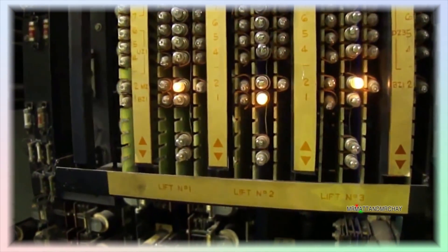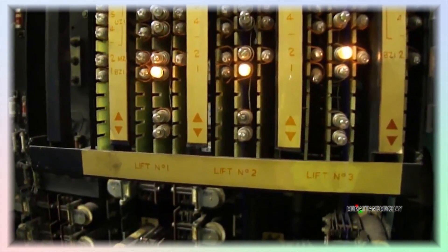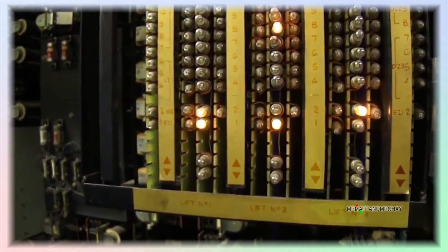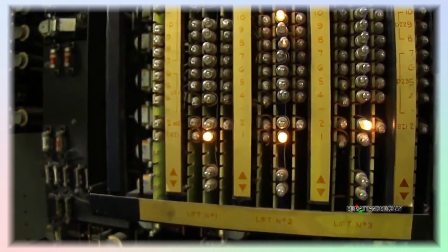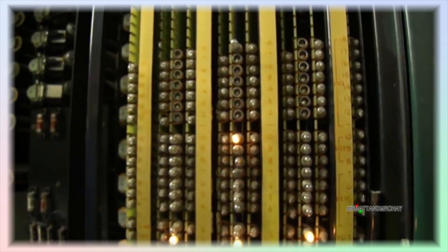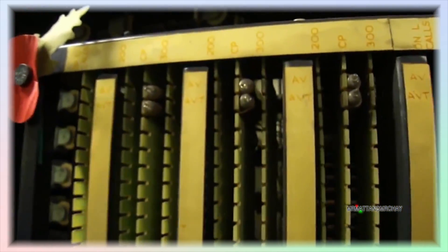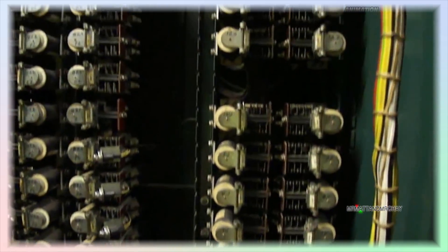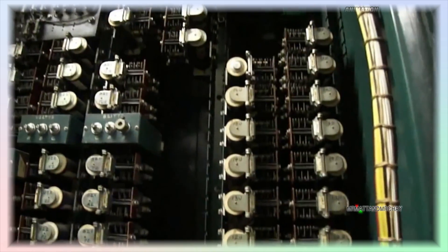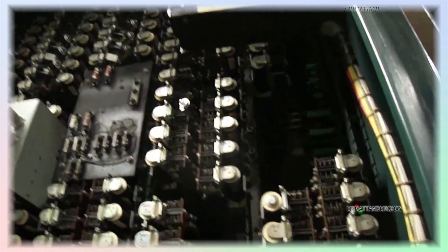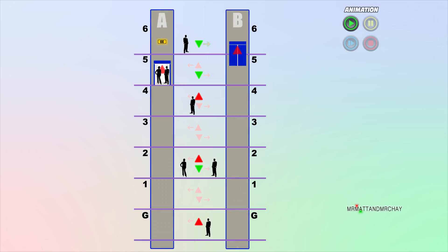As an example, this eighteen floor may have been grouped. Low rise, mid rise and high rise. This simplifies the logic involved. Place a call and the lift waiting within that sector would respond. You also have to bring costs into mind. For a building with not many floors, less relays, less complexity means less costs. Is it such a big deal that two lifts respond here?